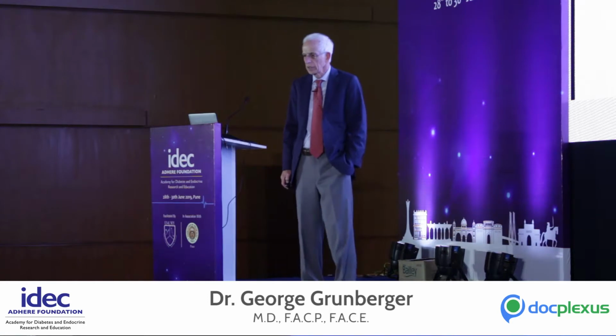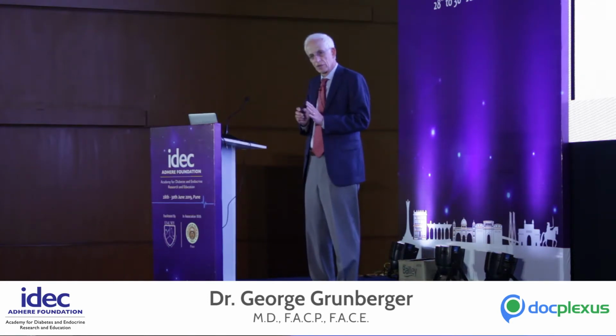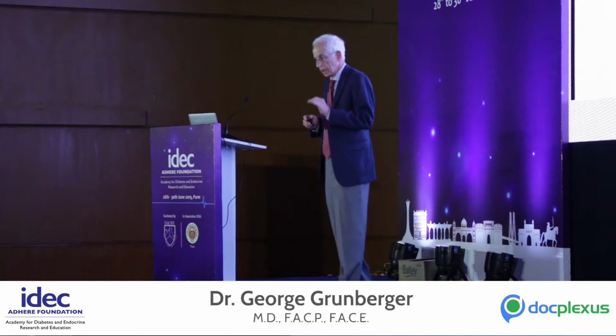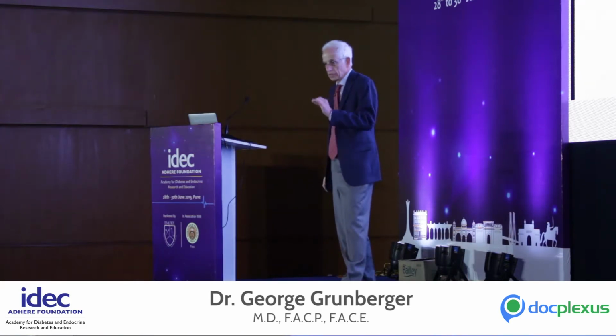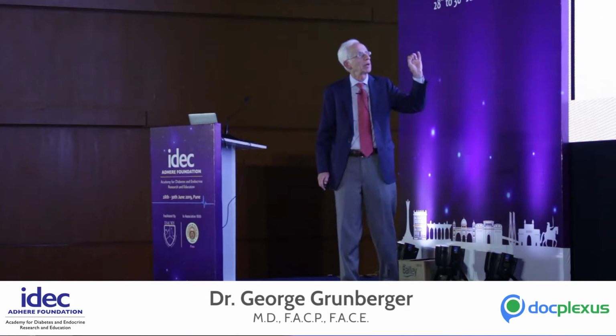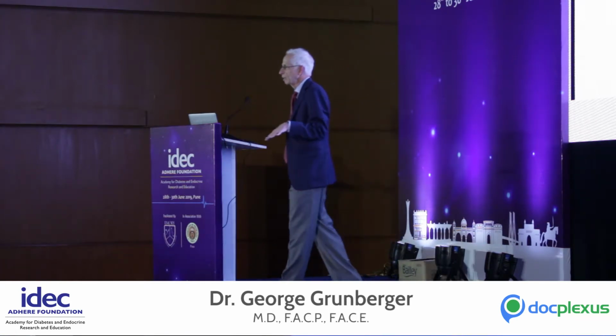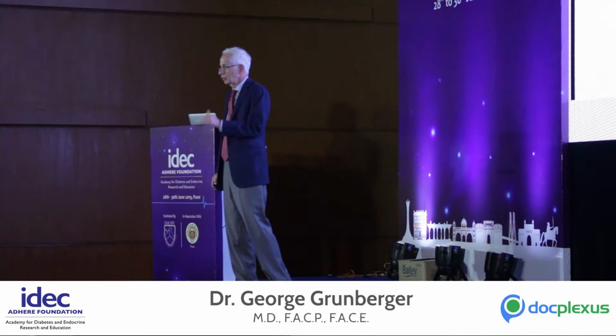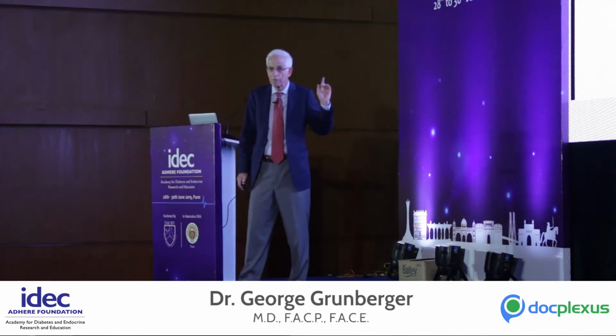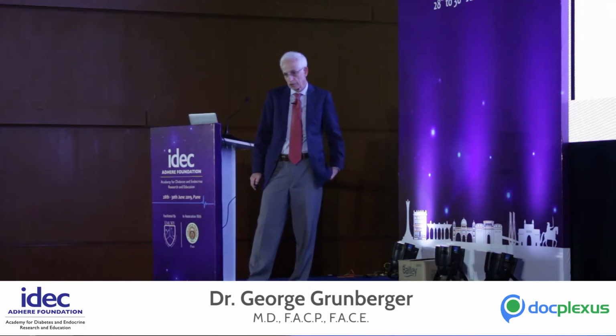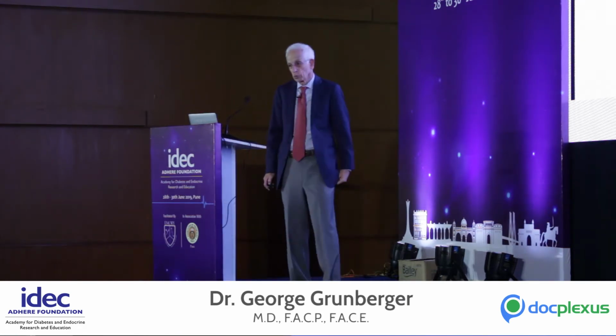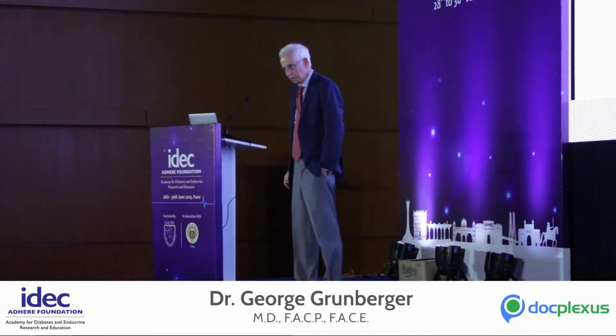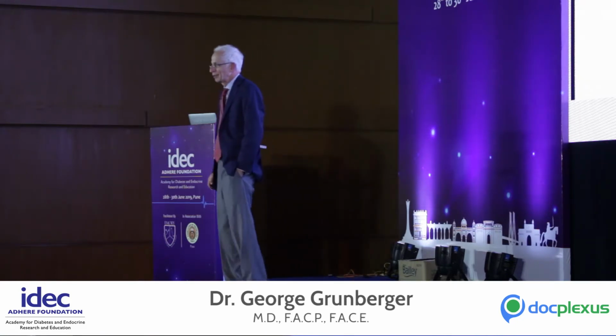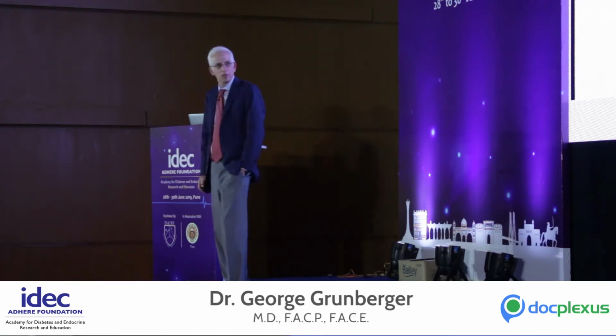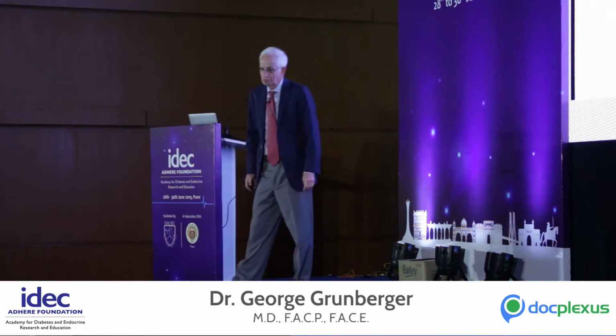And again, the device then sends directly all the report data to your smartphone. How accurate is it? Well, again, if you look at this error grid, it's quite accurate because over the 90 days, 100% of readings are in the safe range. And if you look at the famous MARD, again, remember, anything less than 10% is accurate enough that you can make decisions about treatment based on the data, and it's certainly below the 10%. And actually, we were the first ones in the Midwest to have a patient with a sensor inserted. And people actually like it because they don't have to worry about changing sensors, and we basically have to do it for them every 3 months.